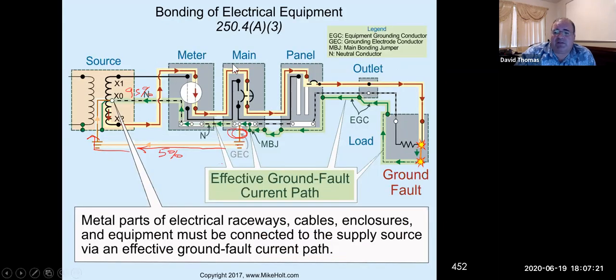But I will tell you, going back to this one here, if you are working on a system, the best thing is to flip the main breaker. And if you want to be overly cautious, you can actually pull the meter. Pulling the meter off of there will cut all electricity. Ultimately, you don't want that to happen, but if you pull the meter off the socket, it will cut the power from the meter box all the way into the main, to the panels and all that. So that's like an ultimate shut off.